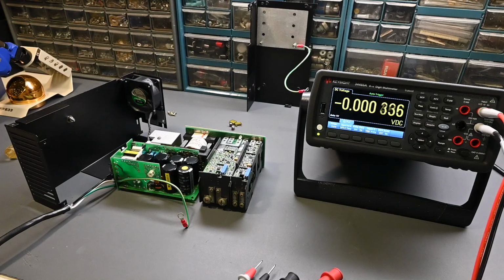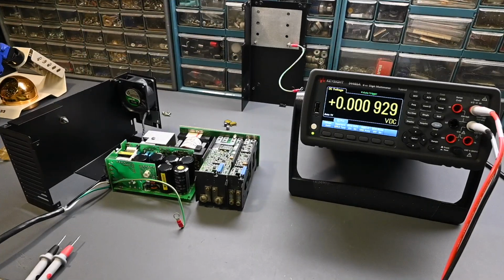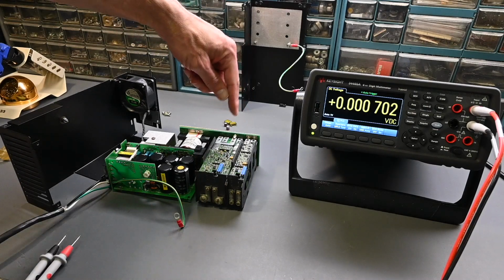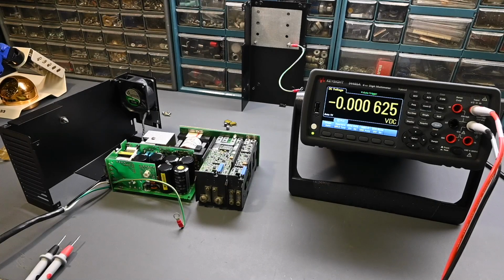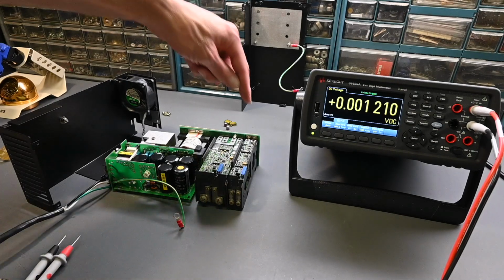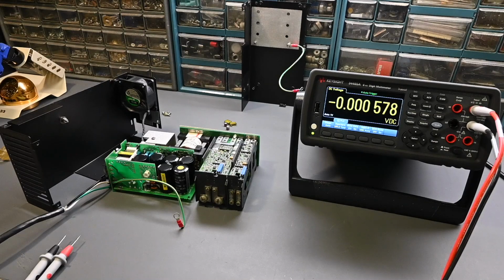Let me continue on with some more troubleshooting, looking at this area, and see if I can narrow down which component is actually giving us a problem. Alright, while the power supply has decided to cooperate, let me take a reading on the AC input to both of these modules, curious to see what the value actually is. It should be an AC voltage at 100 kilohertz or close to that value, but I don't know what the voltage is. There's no specifications of what that voltage actually is coming into these modules, so let's find out.